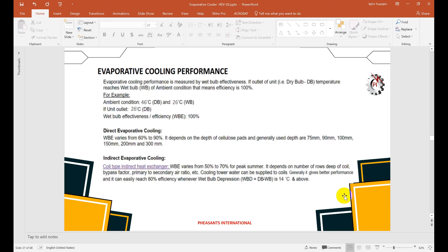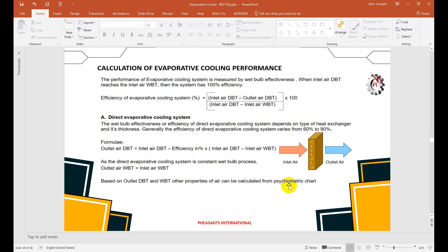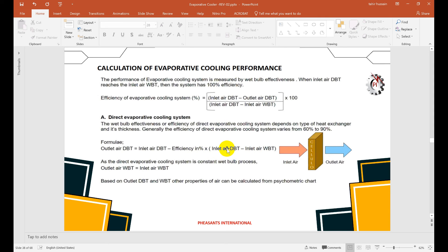Heat exchanger efficiency in indirect evaporative cooling largely depends on the wet bulb depression — the difference between dry bulb and wet bulb temperature. If the difference is more than 14°C, we can achieve 80% heat exchanger efficiency. The efficiency formula is: η = (T_db_inlet − T_db_outlet) / (T_db_inlet − T_wb_inlet). Rearranging, the outlet dry bulb temperature = T_db_inlet − η × (T_db_inlet − T_wb_inlet). This allows us to calculate the outlet temperature from the evaporative cooling unit.